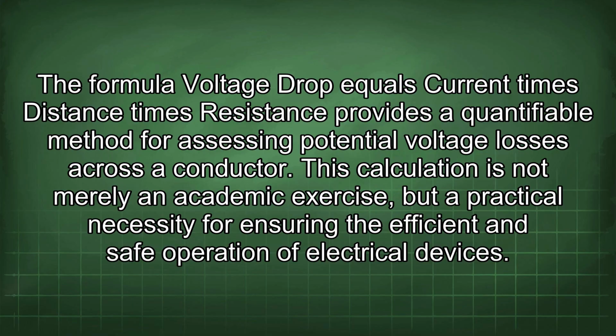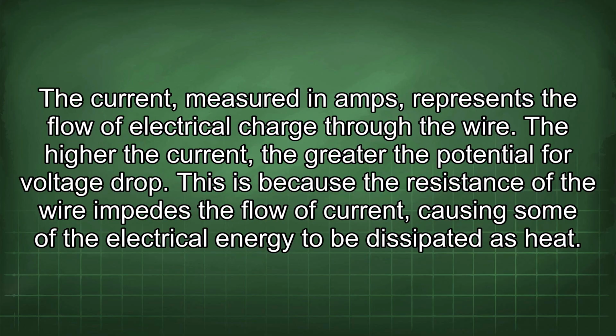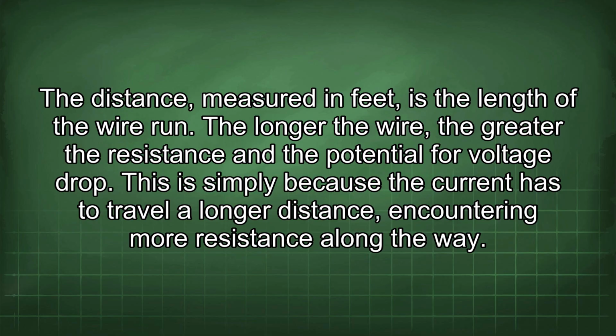voltage losses across a conductor. This calculation is not merely an academic exercise, but a practical necessity for ensuring the efficient and safe operation of electrical devices. The current, measured in amps, represents the flow of electrical charge through the wire. The higher the current, the greater the potential for voltage drop. This is because the resistance of the wire impedes the flow of current, causing some of the electrical energy to be dissipated as heat. The distance, measured in feet, is the length of the wire run. The longer the wire, the greater the resistance and the potential for voltage drop.